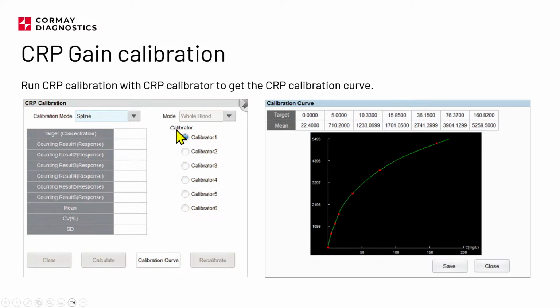So we have a calibrator 1, and in the box we also have a calibrator 1. For calibrator 1, you need to put a target, and as I said, you need to repeat each measurement minimum 2 times. Right? You can do this even 6 times if you like, but in my opinion, 2 times is a good number. It should give you correct calibration. And this step should be done for each level, right?